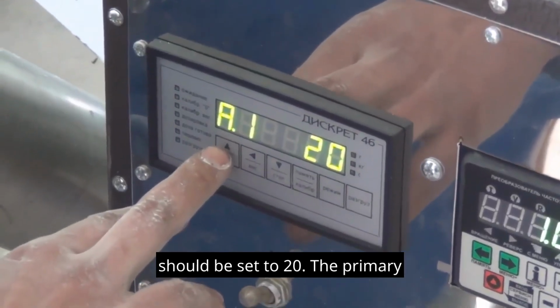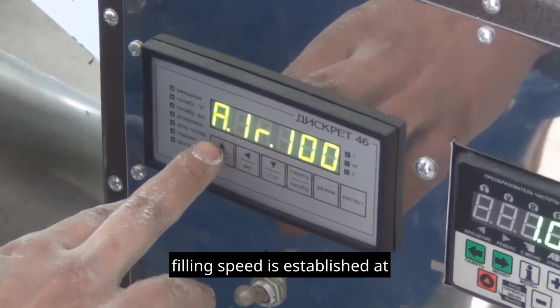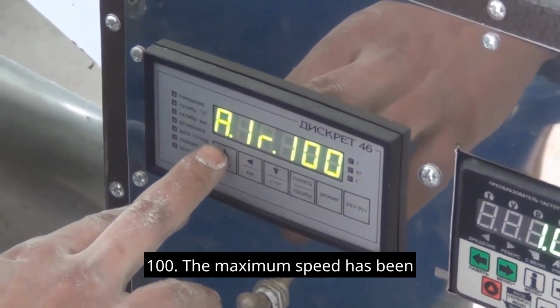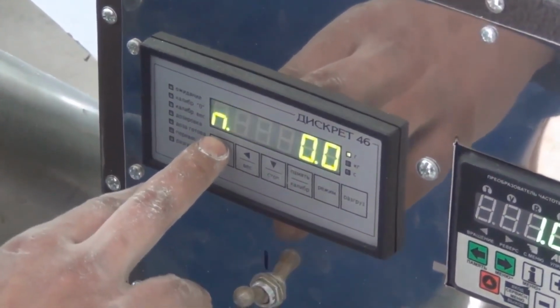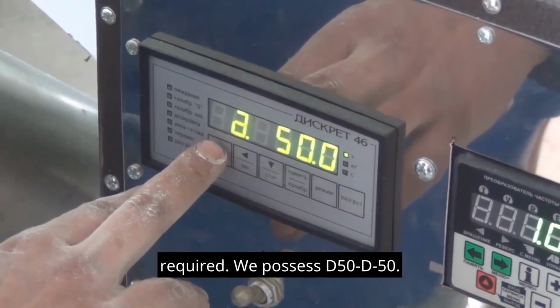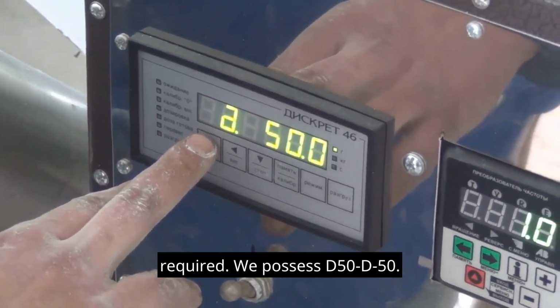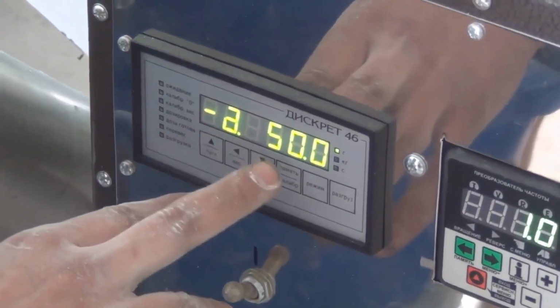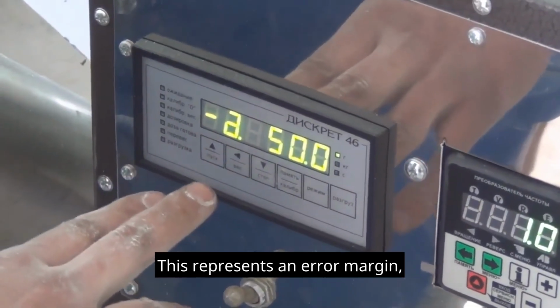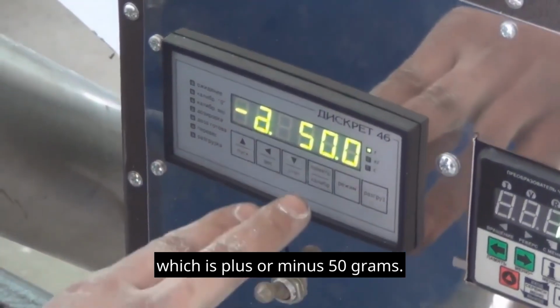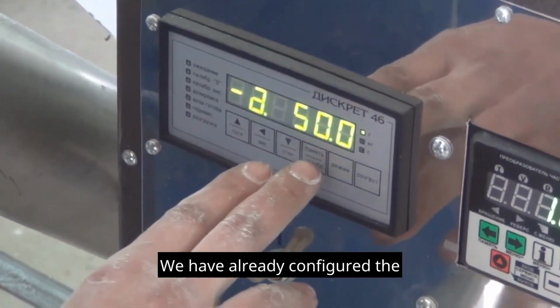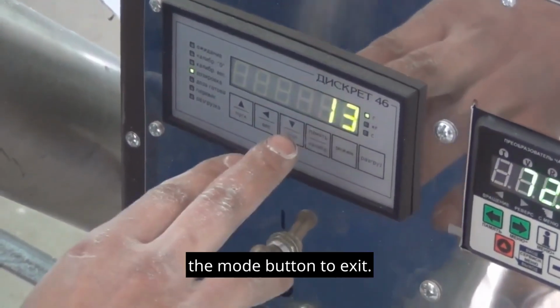Then the supplement speed should be set to 20. The primary filling speed is established at 100. The maximum speed has been configured. Additional parameters are not required. We have D50, D50. This represents an error margin of plus or minus 50 grams. We have already configured the primary parameters. Please press the mode button to exit.